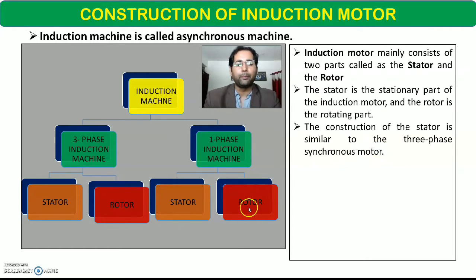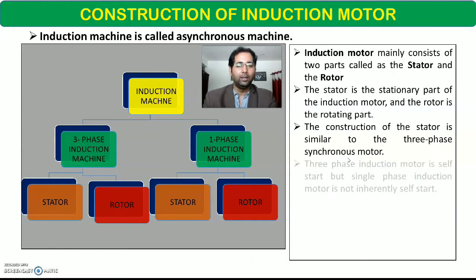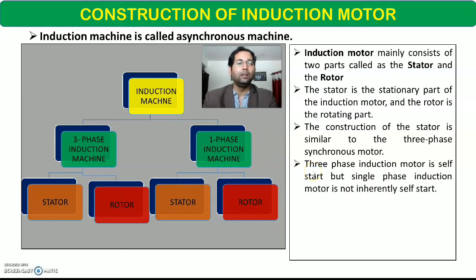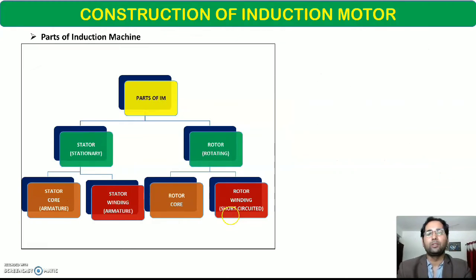Induction machine में एक major difference है — induction machine में rotor permanently short-circuited होता है, जबकि synchronous machine में rotor short-circuited नहीं होता. Plus induction machine singly excited machine होता है — rotor को हम supply नहीं देते. Synchronous machine double excited machine होता है जिसमें हम rotor को भी supply देते हैं. Three phase induction motor self-starting होता है, लेकिन single phase induction motor self-starting नहीं होता. In 95% industrial applications, three phase induction motor is generally used. इसके पीछे reason है its rugged construction, by nature यह self-starting होता है, इसकी maintenance low होती है, और सबसे important इसका operation काफी reliable होता है.